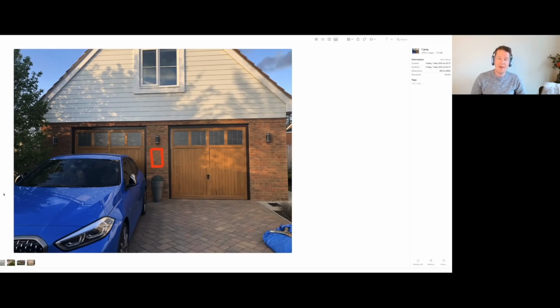I just thought I'd share this with you because this is a scenario we come across more often than you might think. Particularly customers asking if we can wire from their existing garage consumer unit — that happens a heck of a lot. And most of the time, 95% of the time, we can't run off the existing garage consumer unit because the supply installed to it is just not adequate. It's very rare that anyone will install a 63 amp supply to a garage, or a 50 amp supply to a garage, and that's kind of the minimum you need in order to be able to run an electric vehicle charging point from it.